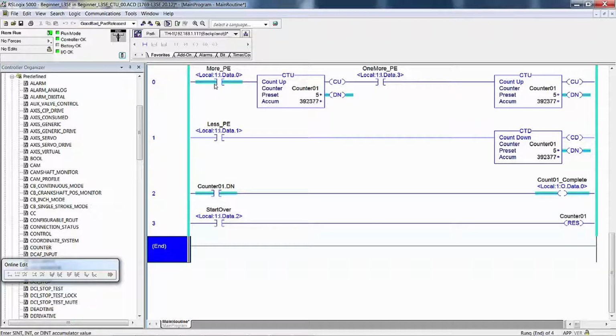this is incrementing. The first time 0 goes true. We'll do these start over thing just so we have a clear shot here. So if I turn this on, that goes true, that increments. This is false. It clears the false true memory, if you like, the one shot. And then the next scan around, it can count again. So you basically, by doing this, have turned it into a scan counter. You don't want to do this. So I'm going to turn that off. And of course, if I go back here, turn that on, and then I turn on this one, see, now it stops doing that.